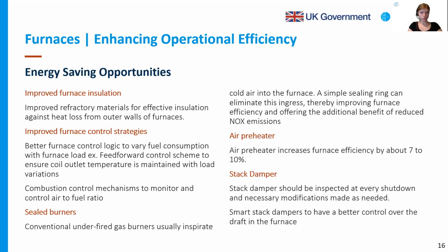Improved furnace insulation is associated with retention of heat. Improved refractory materials give effective insulation against heat loss from the outer walls of furnaces. For a sizable furnace, this is actually as simple as a visual inspection, because when refractory materials are worn out or becoming poor, not doing their job, it leads to development of hot spots, and this can actually be visually observed in the form of discoloration on the exterior walls of furnaces. Especially when you have box type furnaces or reformer furnaces, this discoloration is very obvious, and that's when you need to consider replacing the refractory material in the next shutdown to prevent further hotspots or deterioration, in addition to, of course, heat loss from the furnace walls.